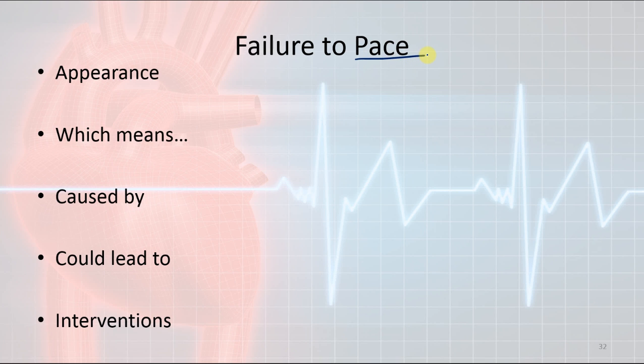Now let's talk about a failure to pace. When you have a failure to pace, what you see on the monitor is a missing pacer spike where there's supposed to be one. So for example, if you have a pacemaker that is set to not let the heart go below 60 beats a minute, and the heart is going below 60 beats a minute, that means that the pacemaker is failing to pace. What this means is the pacer is not firing as it's programmed.